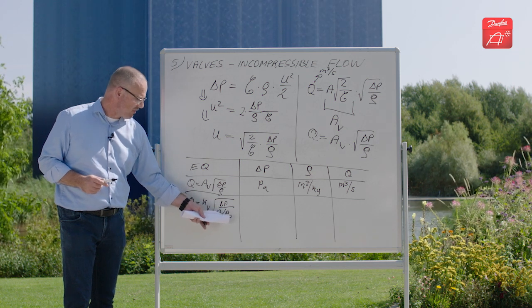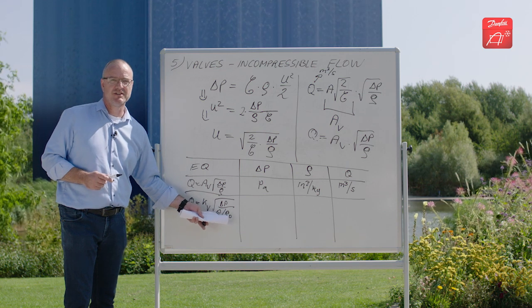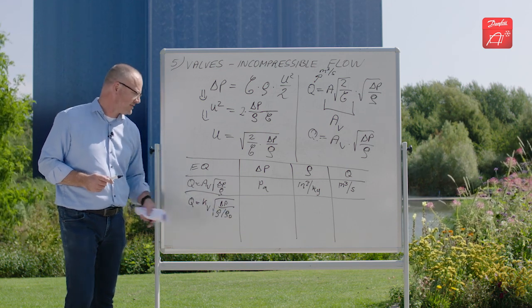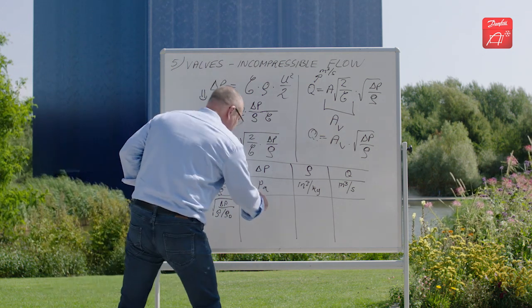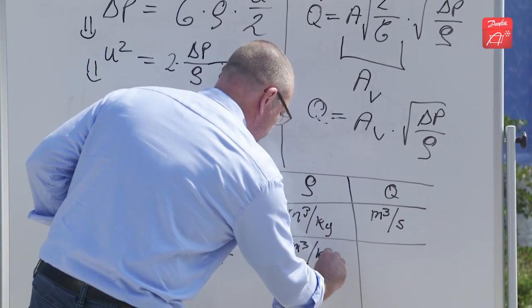So this value, density zero or rho zero, is just water at 20 degrees, so it's a density of a thousand kilograms per cubic meter. If you use this equation, the pressure drop is expressed in bars, the density is still kilograms per cubic meter, and the flow is in cubic meters per hour.